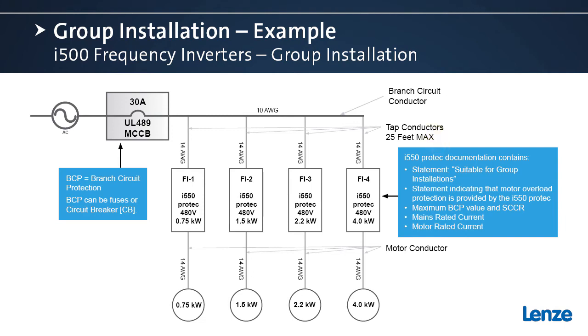This has to do with the relationship between the wire gauge, the wire size of the tap conductors versus the branch conductors. If we chose to, we could use also 10 gauge wire for the taps. And if we did that, there would not be any restriction on the length. In this example, we calculated that we could use 14 gauge, and we did use 14 gauge. That 14 gauge, of course, is a little bit smaller than the branch circuit conductor, which is 10 gauge. And that drives a limitation, in this case, of 25 feet maximum. These taps can't be any more than 25 feet long. Again, if you wanted to match the same gauge as the branch conductor, that restriction goes away. But there are length limitations in both the NFPA 70 and the NFPA 79 with regards to tap conductor length, and those restrictions are based on the relationship of the wire size between the tap conductor and the branch conductor.